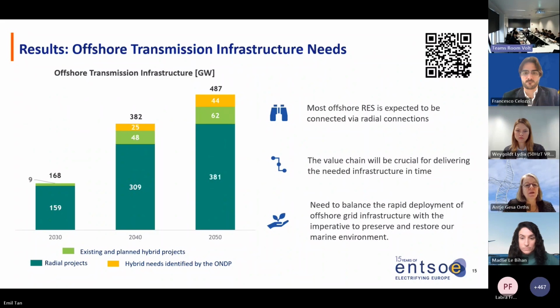These can vary. We investigated different technical configurations, meaning either we have DC links with offshore DC breakers, or we don't have DC breakers. They are important in order to isolate faults. If there is any fault, we need to isolate it so we're not forced to shut the entire offshore network down and lose the ability to transport anything to shore. Therefore, DC breakers are important.